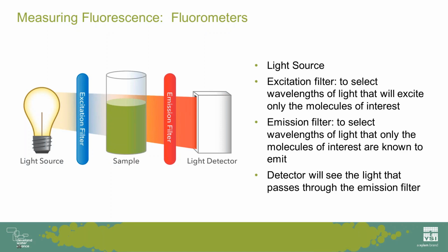Stick with me. So I'm going to back up here and talk again about fluorometers. Fluorometers have been used for decades in the laboratory. Every fluorometer has a light source, typically some type of lamp that emits a wide range of light wavelengths. The fluorometer is going to have an excitation filter, shown here on the left, that narrows the range of wavelengths to include those that can excite the molecules of interest in your sample.